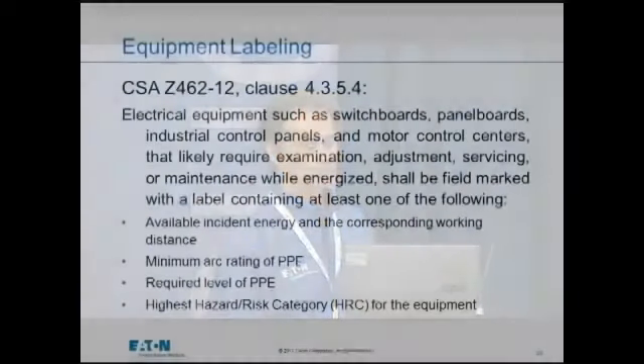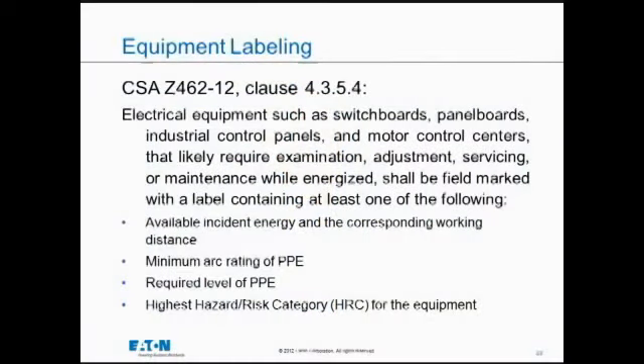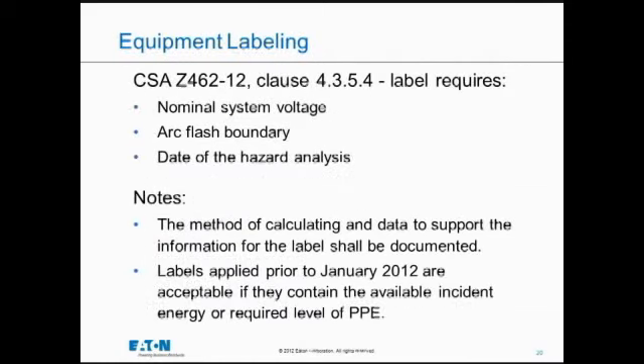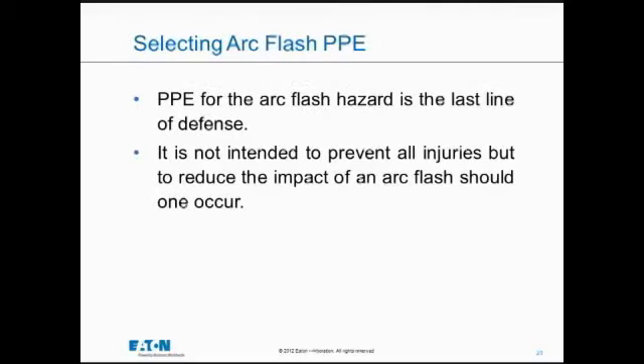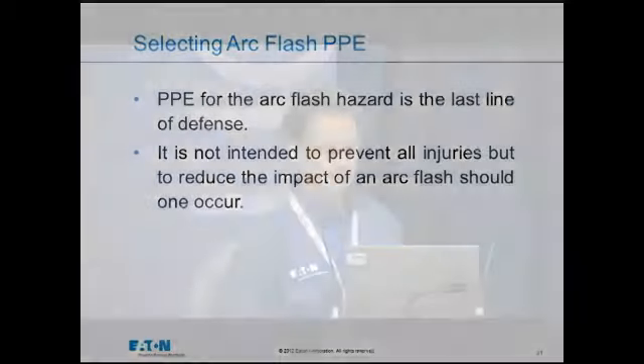Is it current? Once you know what the hazard is and you know what your working distance is, you can select your PPE. And there's always a caution that it's not like you're putting a Superman suit on. It's not going to protect against everything, but it's there to prevent bodily harm should an arc flash occur. And it doesn't protect against things like shrapnel in some cases. The cloth in arc-rated clothing is not ballistic material. You can get some Kevlar sewn into the material, but it doesn't protect against shrapnel and some of the other injuries that could occur. It's protecting against heat hazard at this point, in most cases.